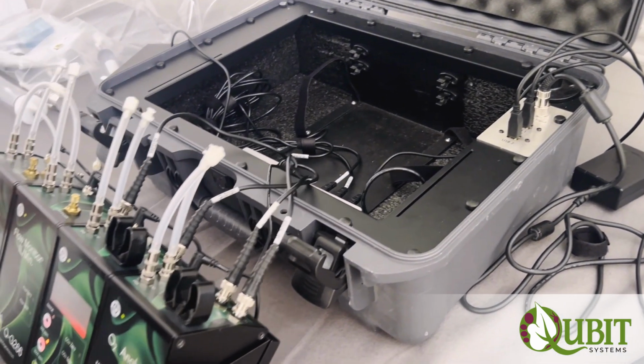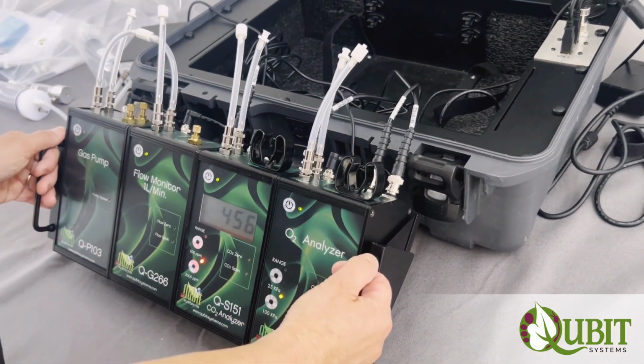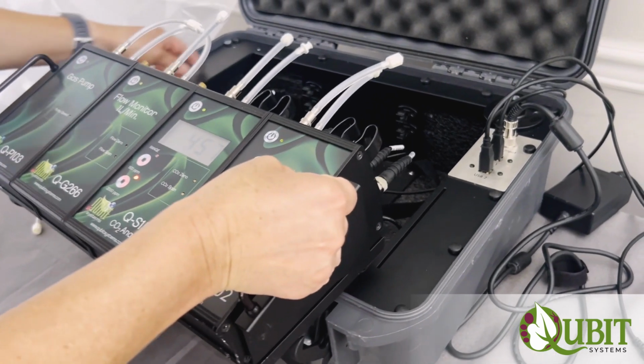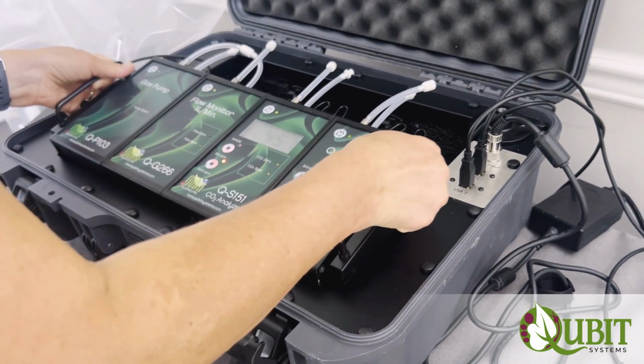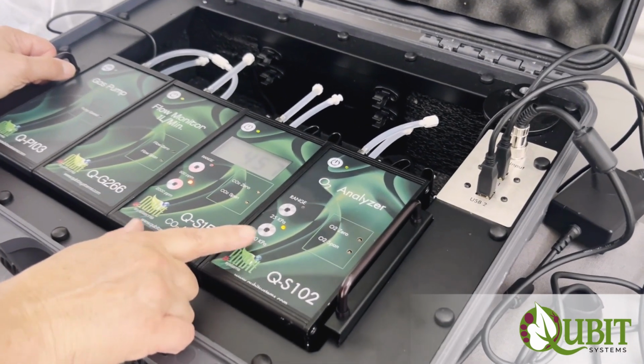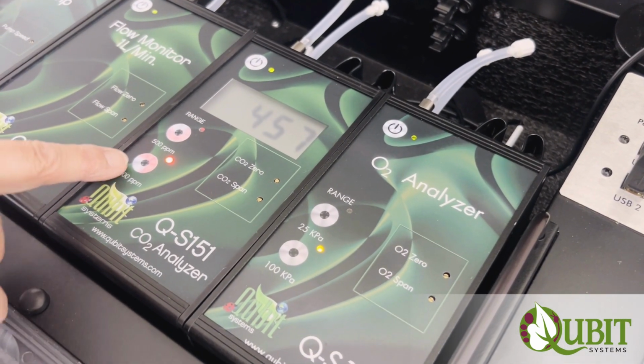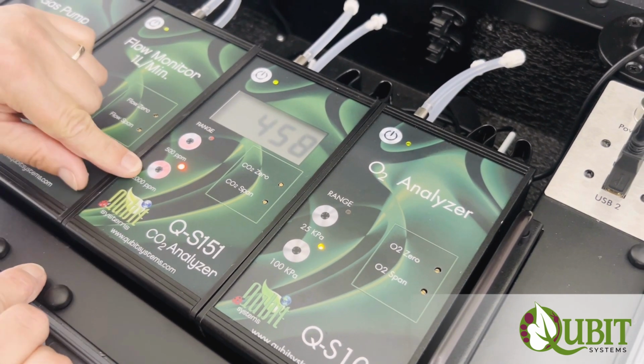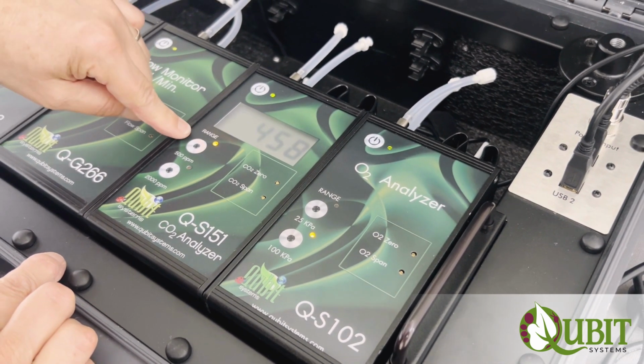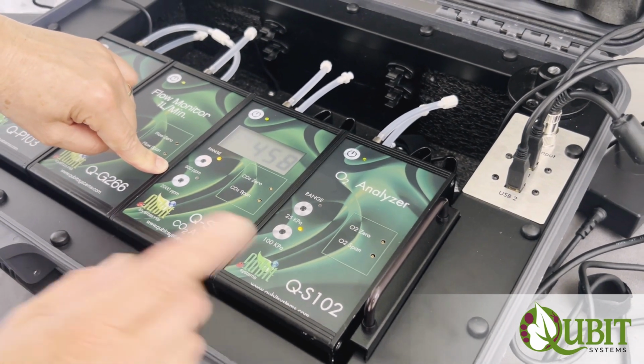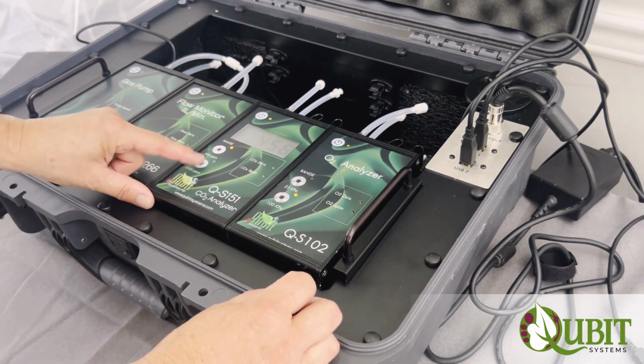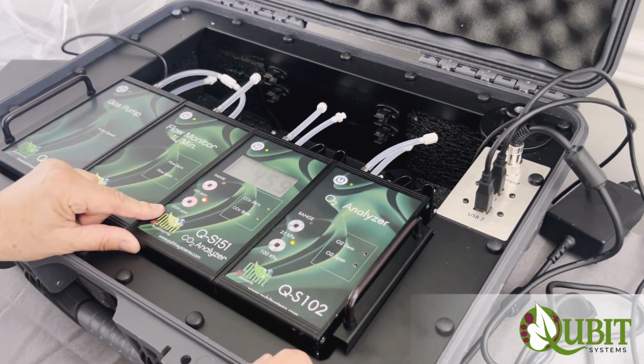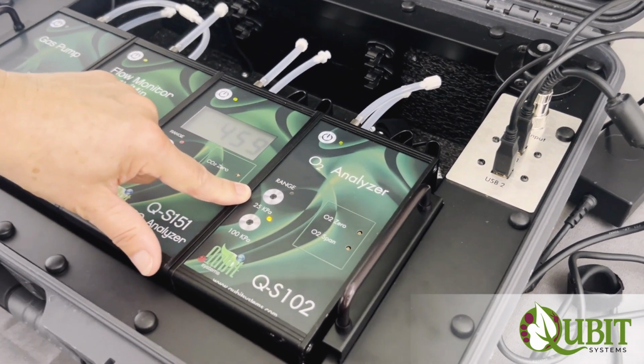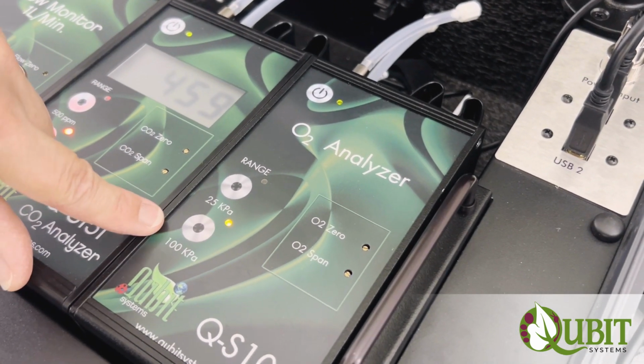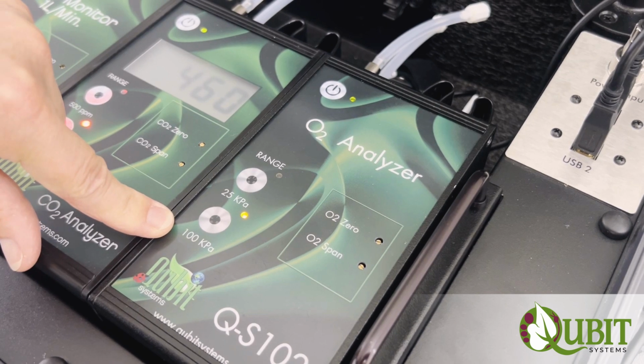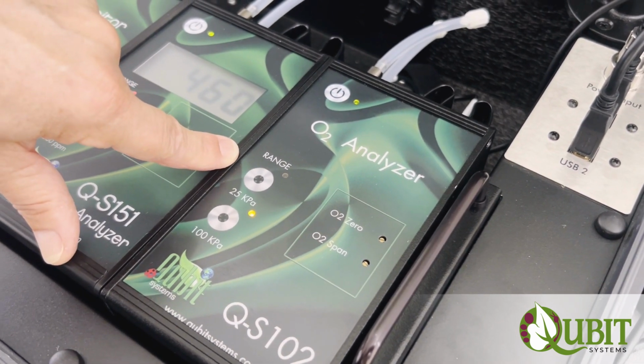The other thing to check when the readings are incorrect is that we have correct ranges selected. You will find that both the CO2 analyzer and the oxygen analyzer have two different range selectors. There's 2,000 parts per million, which is activated right now for CO2, and 500 parts per million. The two ranges require different calibration in that software, and the Q Box RP1LP is set up to be used with 2,000 parts per million range and with 25 kilopascal range for oxygen analyzer. So this is right now incorrectly selected. It's 100 kilopascal range selected instead of 25. So you need to change that.